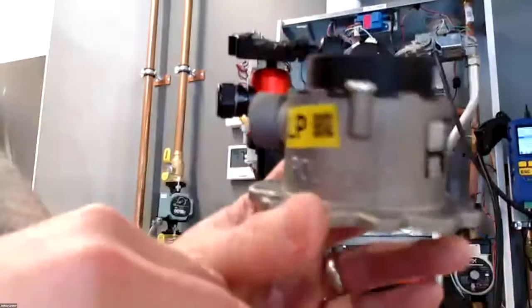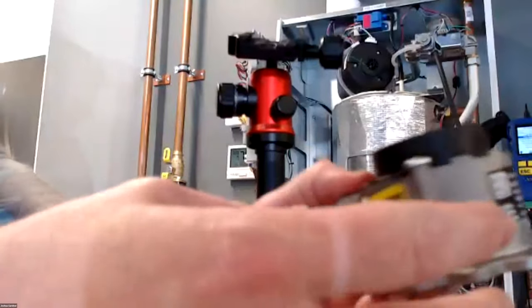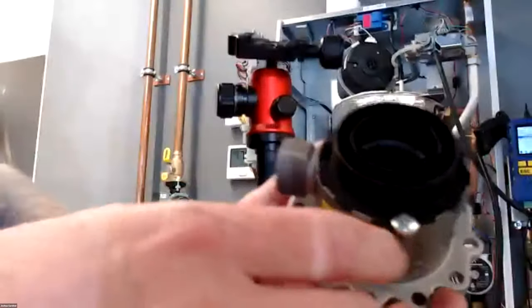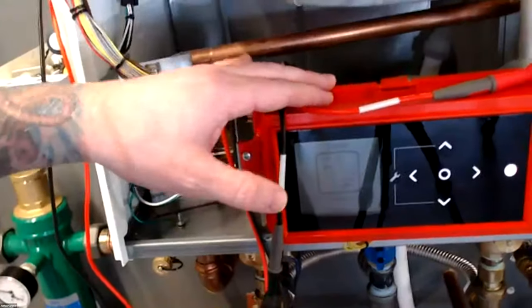So the units come with the natural gas orifice installed. The LP orifice will be in the box. So you'll swap these out, all right? This is the only mechanical thing we'll swap out. After we swap that out, we're gonna go into the control, and we need to change a setting in the control, the appliance code setting. Also in the boiler, you'll get a sticker, and that sticker will have the LP info. So up here, we have the serial number of our boiler. Down here, we'll have our appliance code. That appliance code will tell the boiler if it's natural, propane, combi, and then what size.